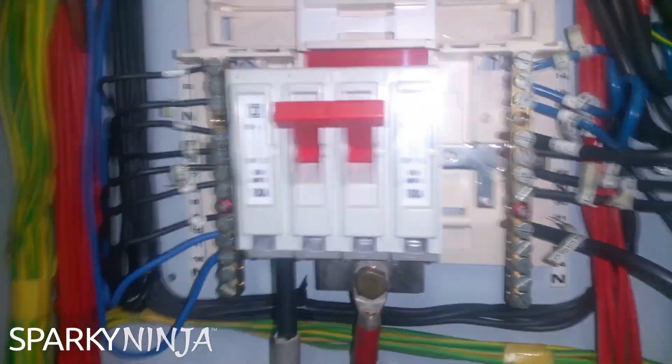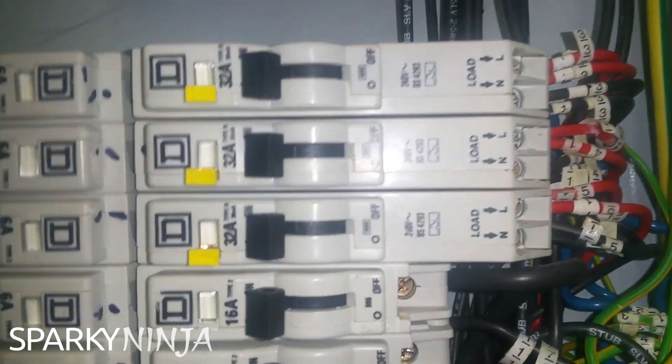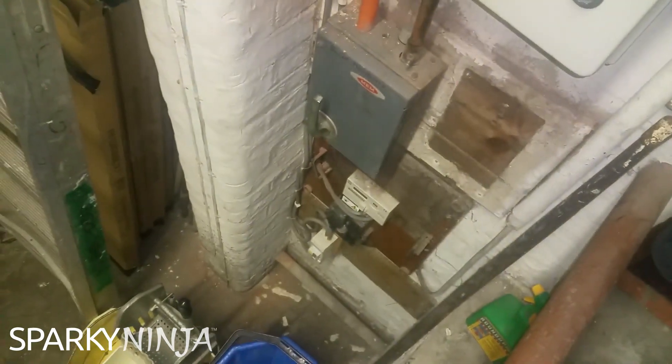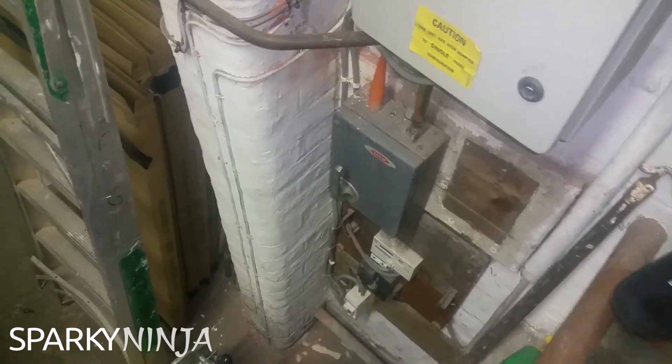Up in the board you've got a load of old BS3871 ones - not a problem - and some BS4293 RCBOs, which again are 30mA, but there's no discrimination with that one down there. So there's no discrimination in any of these RCDs at all.